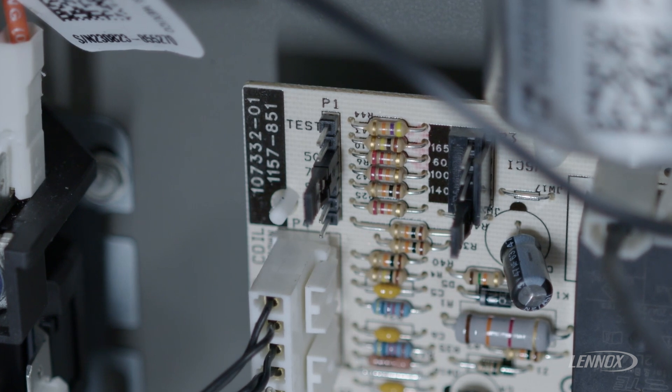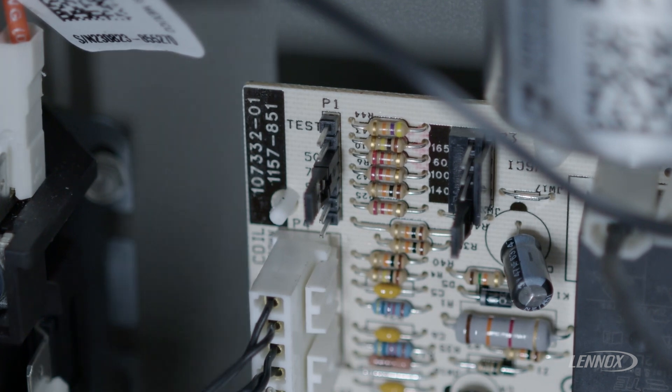So to test the defrost mode, we're simply going to remove the jumper from the defrost termination temperature and place it across the test pins.